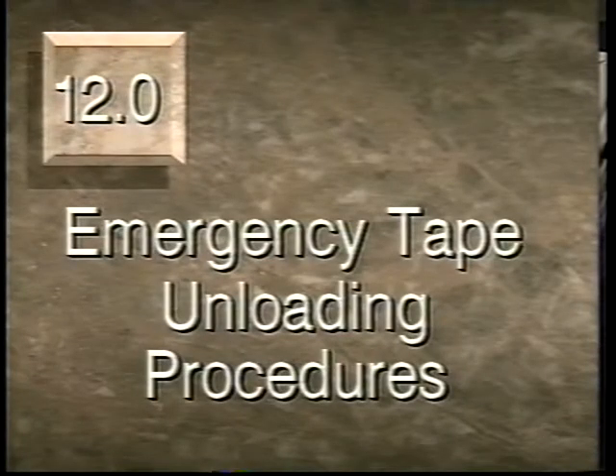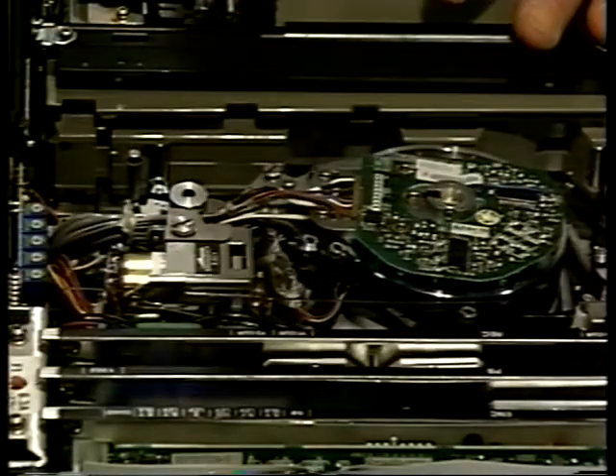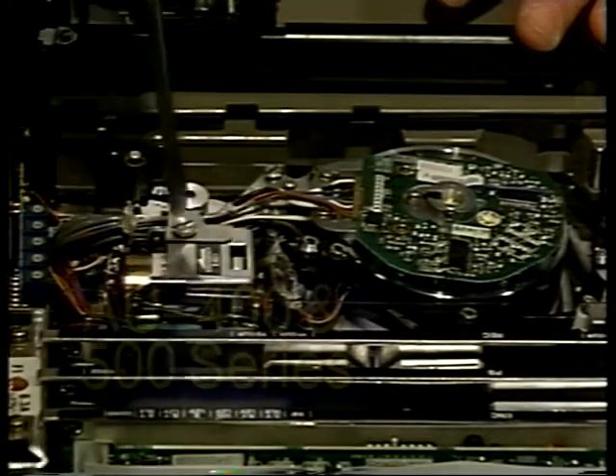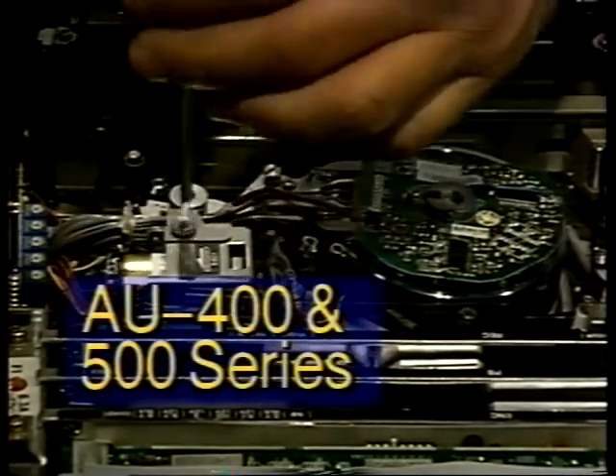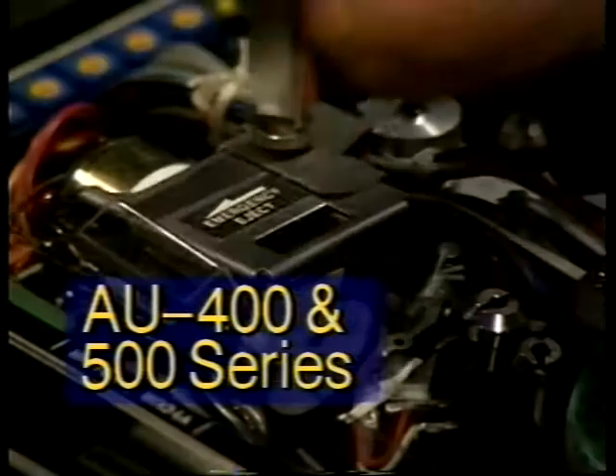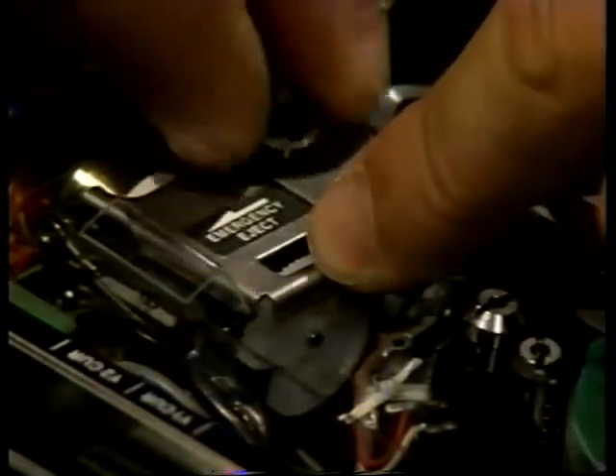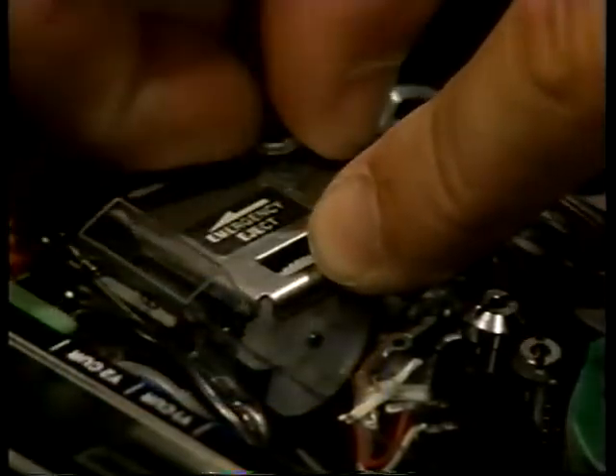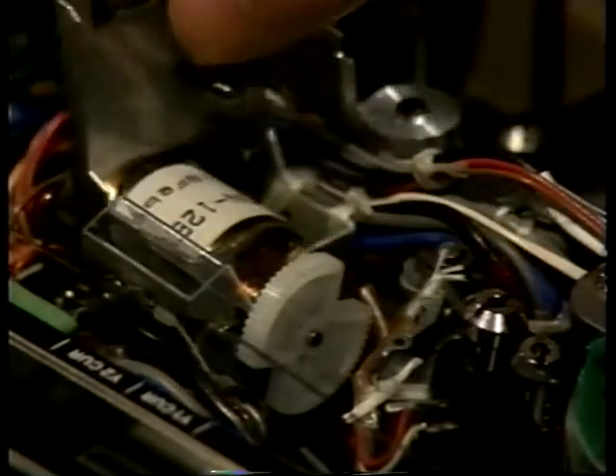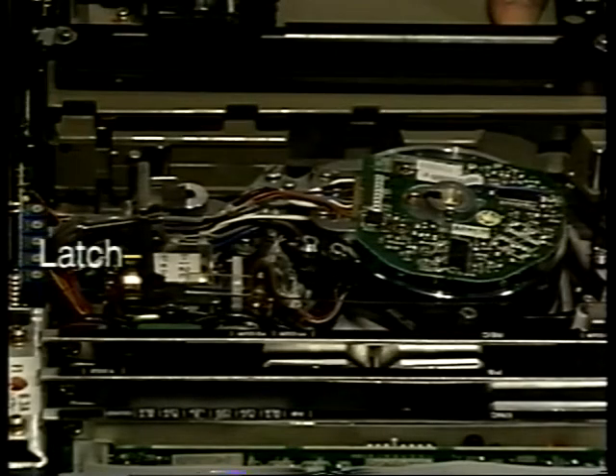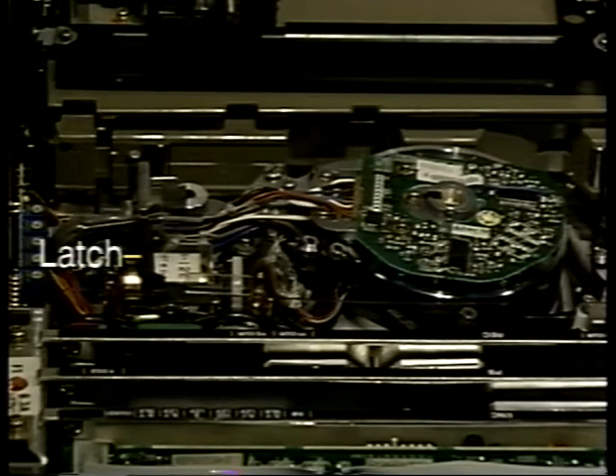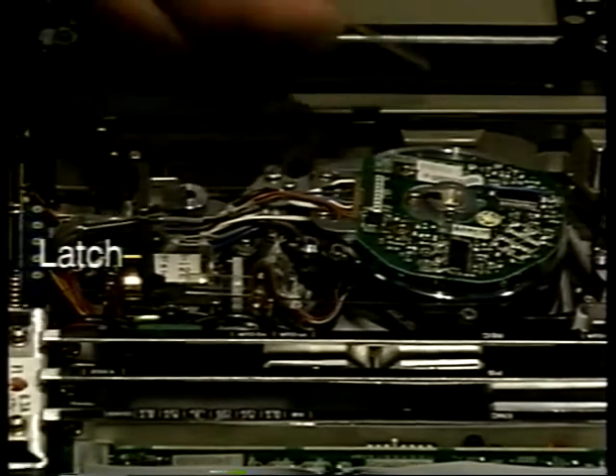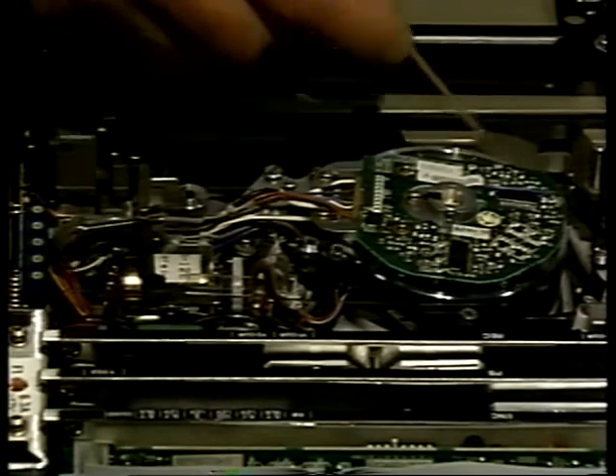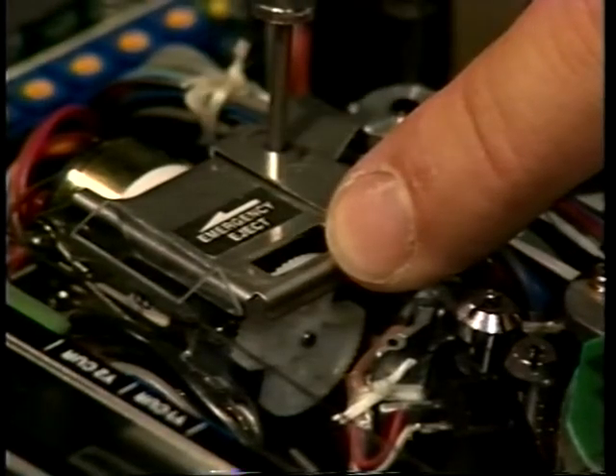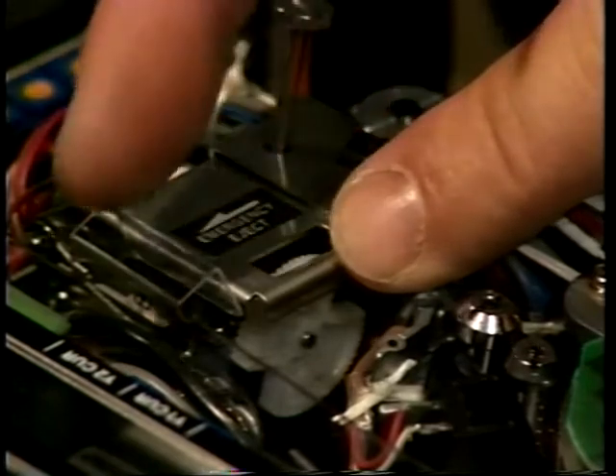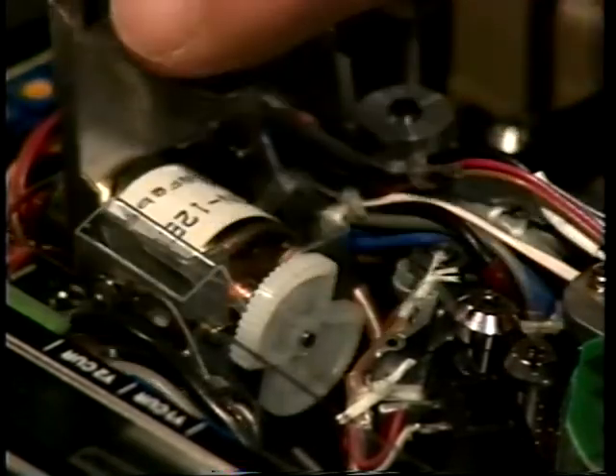Emergency tape unloading procedures. Let's look at the emergency eject procedure for the portable units. For the AU400 and the AU500 series, the procedure is basically the same. Unscrew the emergency eject latch and lift the latch up. When this latch is lifted, it engages a roller onto the gear for the supply reel, which is down in here. An arrow on the latch shows the direction to turn the wheel after the latch is in the up position.